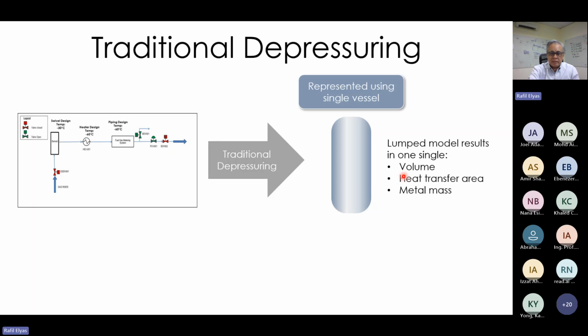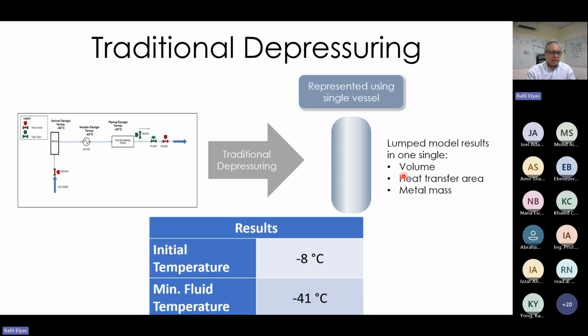So when the customer had actually done this analysis, they found that everything was essentially settled out to ambient conditions. So it was a shutdown, and everything lined out to about minus 8 degrees Celsius. When they ran the traditional depressuring, the lumped depressuring, they found a minimum fluid temperature of minus 41 degrees Celsius. So this was a bit disconcerting.